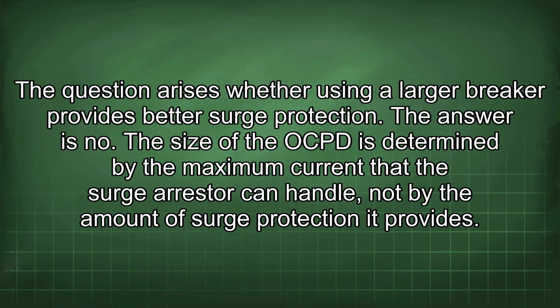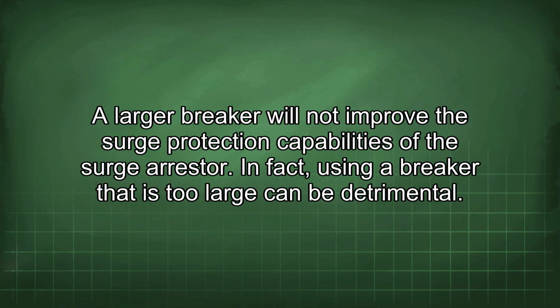The question arises whether using a larger breaker provides better surge protection. The answer is no. The size of the OCPD is determined by the maximum current that the surge arrestor can handle, not by the amount of surge protection it provides. A larger breaker will not improve the surge protection capabilities of the surge arrestor.